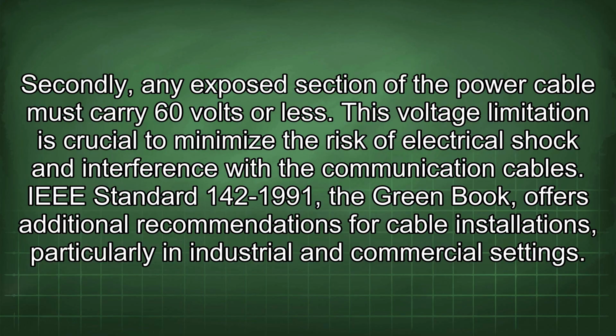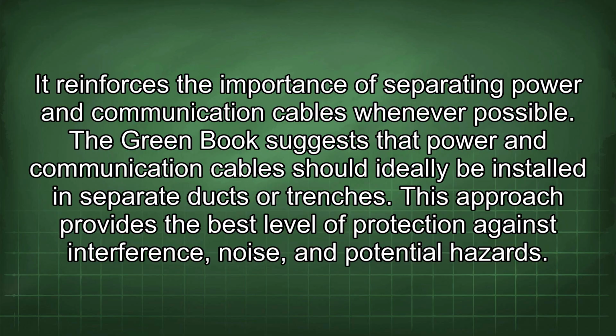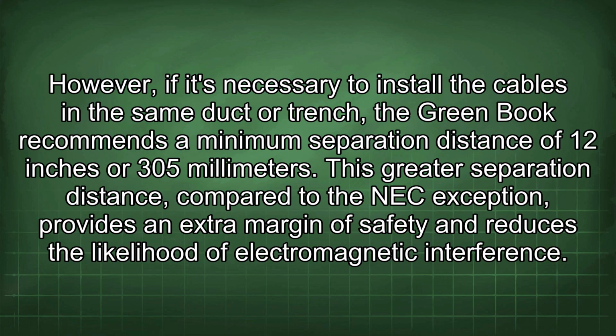IEEE Standard 142-1991, the Green Book, offers additional recommendations for cable installations, particularly in industrial and commercial settings. It reinforces the importance of separating power and communication cables whenever possible. The Green Book suggests that power and communication cables should ideally be installed in separate ducts or trenches. This approach provides the best level of protection against interference, noise, and potential hazards. However, if it's necessary to install the cables in the same duct or trench, the Green Book recommends a minimum separation distance of 12 inches or 305 millimeters. This greater separation distance, compared to the NEC exception, provides an extra margin of safety and reduces the likelihood of electromagnetic interference.